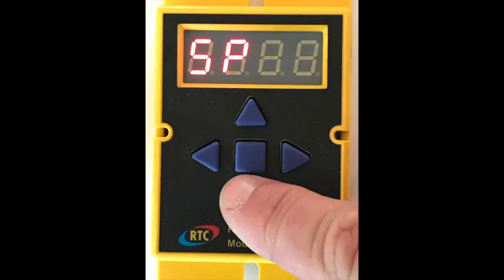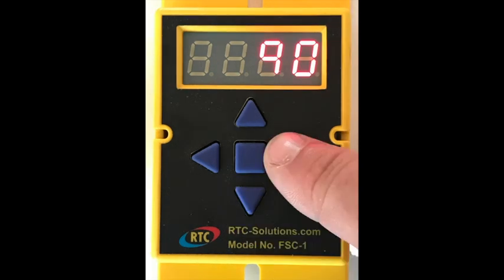The next menu is SP, which stands for set point. This is the speed setting that the motor will run at. The setting is a percentage from 0 to 100%, so a set point of 50 would cause the motor to run at half speed. If all you need to do is change the speed, you can also just push the up or down buttons without entering the programming, and change the speed, then the center button to save it.